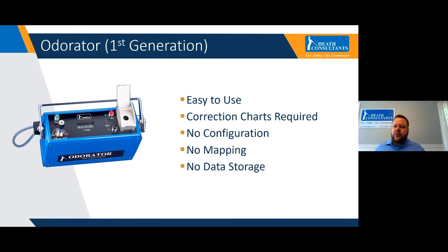It does require correction charts. That means the percent gas on the display may not be accurate based on elevation, pressure, and other environmental characteristics. So a chart is placed on the instrument based on those characteristics, and it must be corrected and correlated to the value on the screen, which adds an extra step and a bit more complication to calculate the odorant test value.